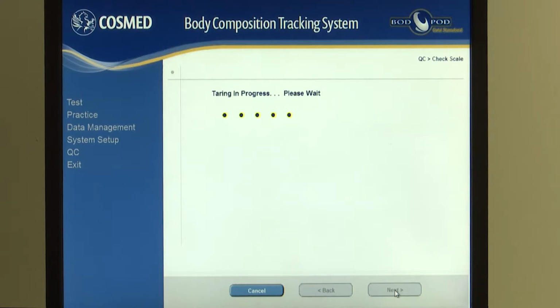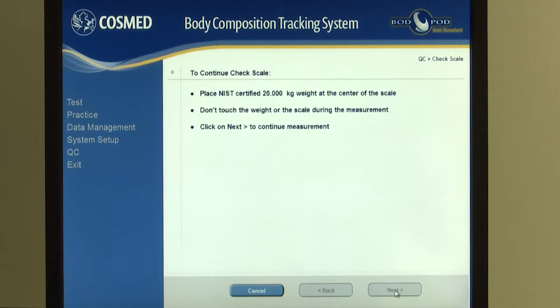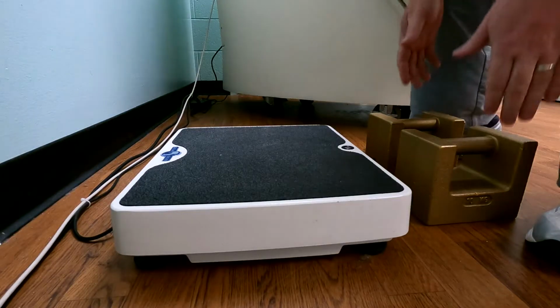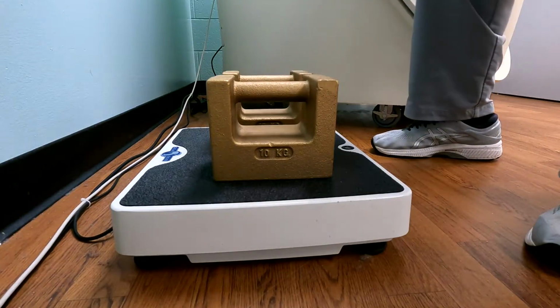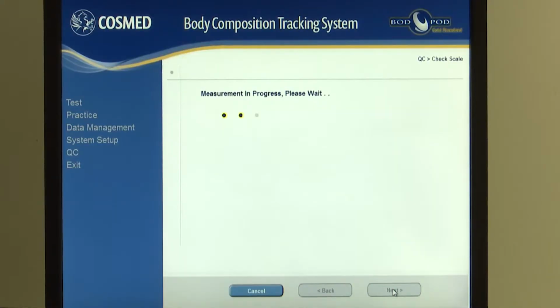This is the check scale portion of the calibration. It is very similar to the scale calibration that was just performed. However, it only requires the weights to be placed and removed from the scale once.